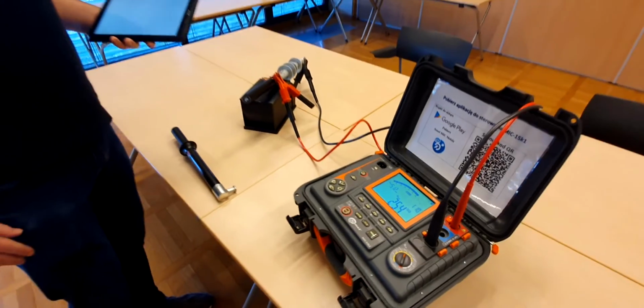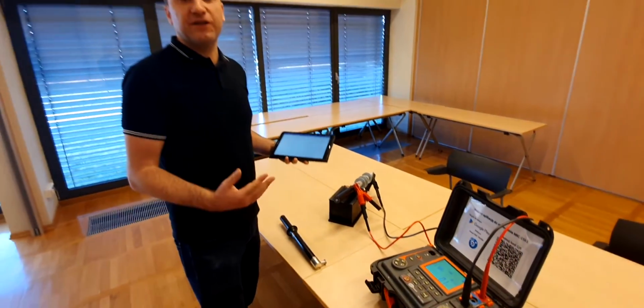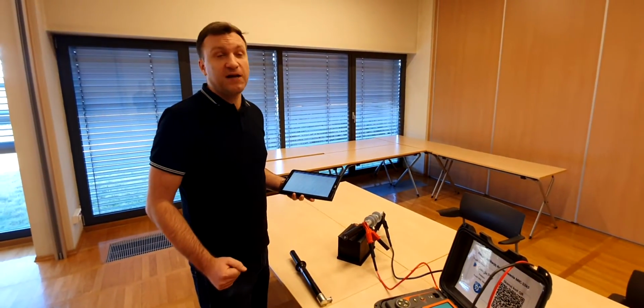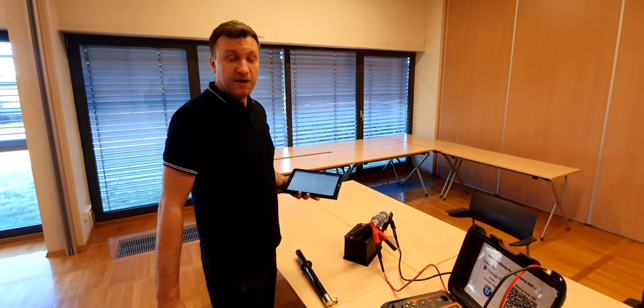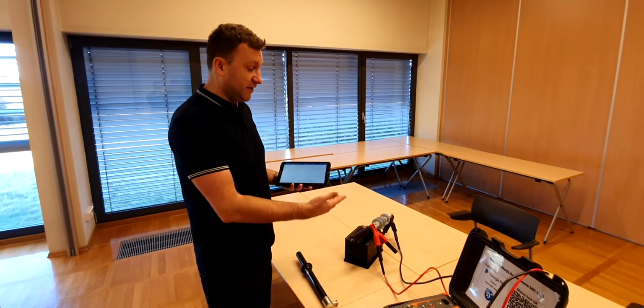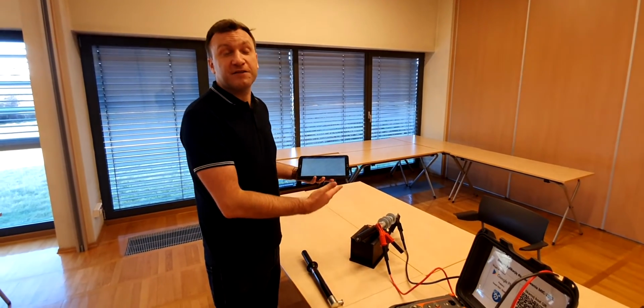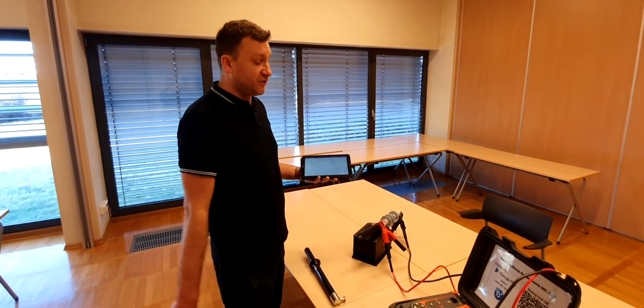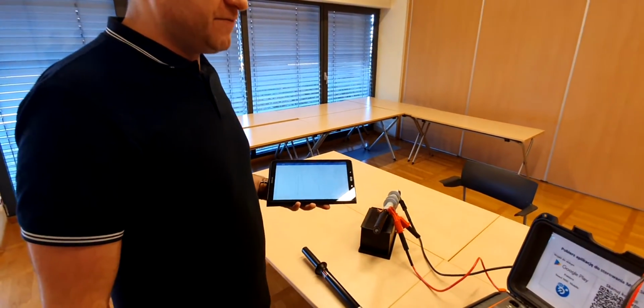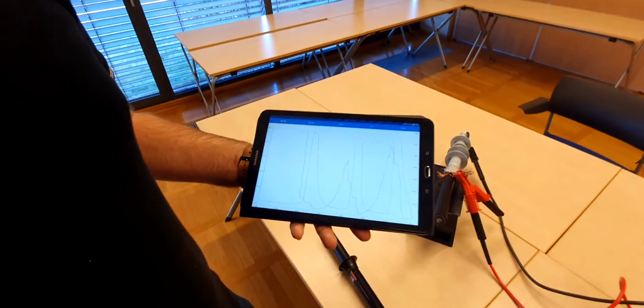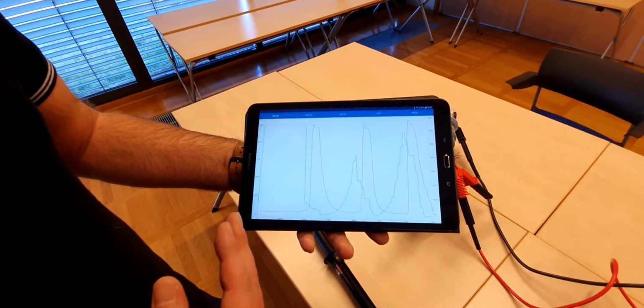So, generally, the measurement has finished. We have some value. It might be above the minimum limit for this cable, and we may think that this cable is okay, that its insulation is in a good condition. However, thanks to the functionality of SONEL MIC-15K1, we know that the cable is not in a good condition.